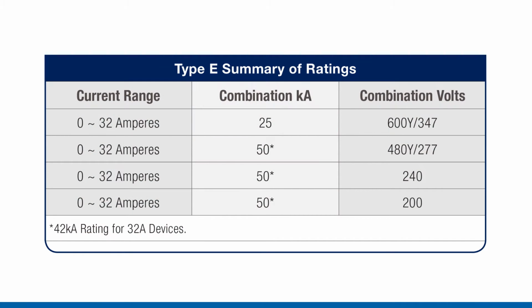Let's talk about how combination motor controllers are rated. They are rated similar to other controllers that are intended for use in motor circuits. They are specified by horsepower and rated by short circuit current rating. For example, a 5 horsepower motor at 480 volts requiring a short circuit current rating of 50,000 amperes at 480 volts.